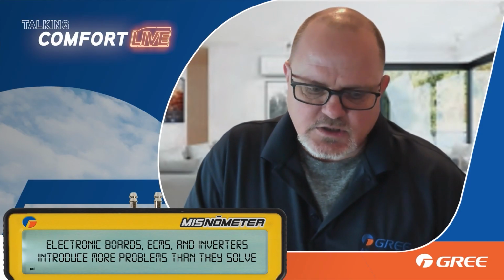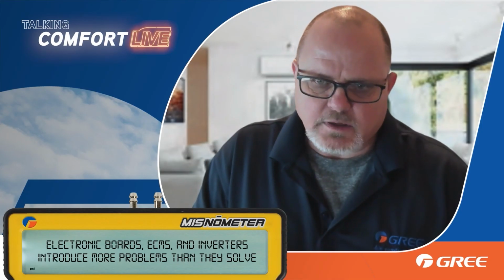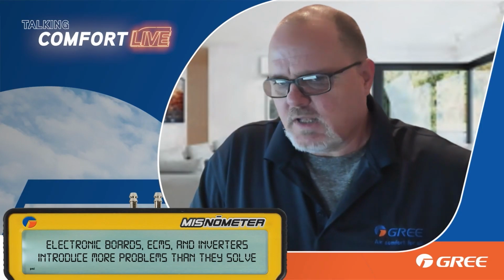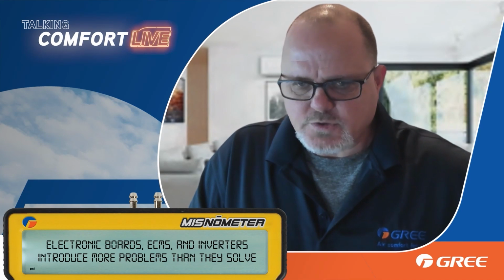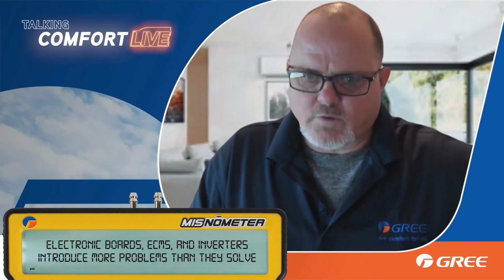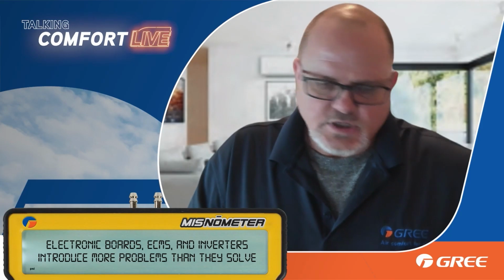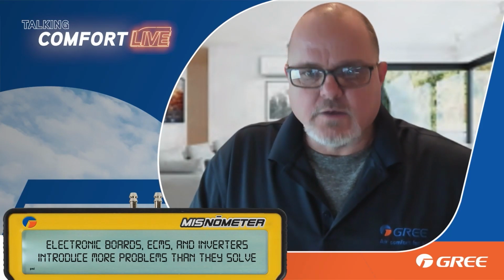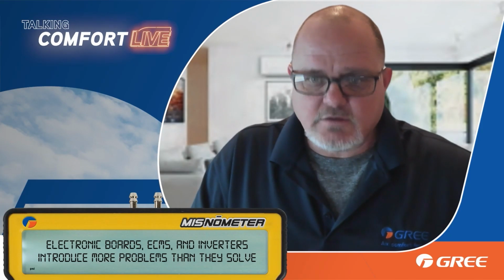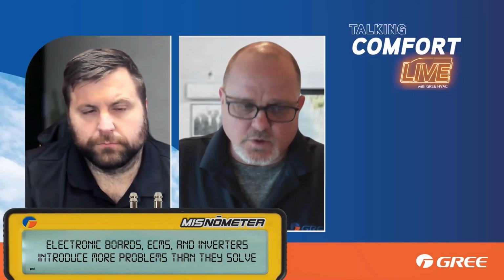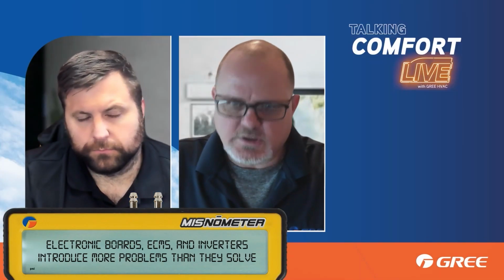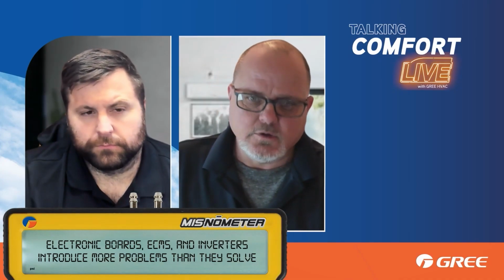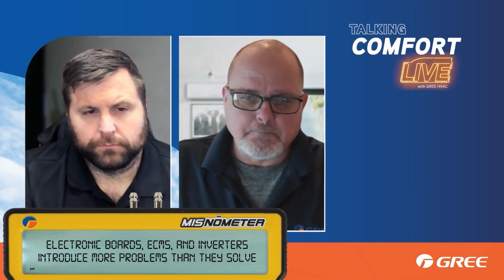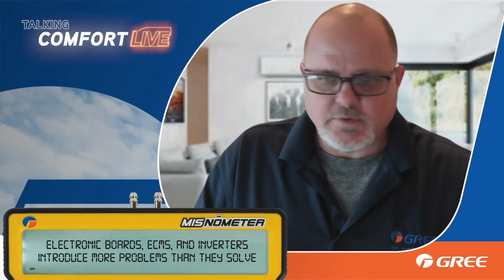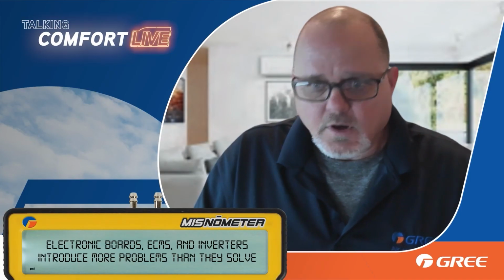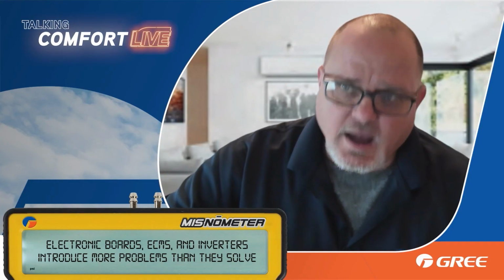So in a lot of machines, like if you're talking standard equipment, if you keep running that machine like that low on refrigerant, you're going to end up with a compressor out on overload. The machine's down. Now the overload cools off, finally resets, and it keeps doing that till we get to the point of, like we just talked about earlier, where you end up overload never resets. We got to replace the compressor, or we end up getting a burnout on the compressor, and now we not only have to replace the compressor, but we have a contaminated system on top of it.